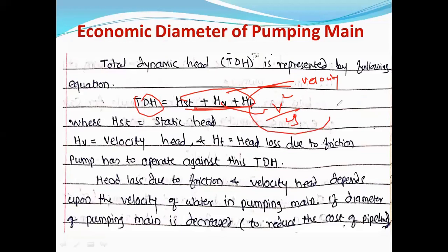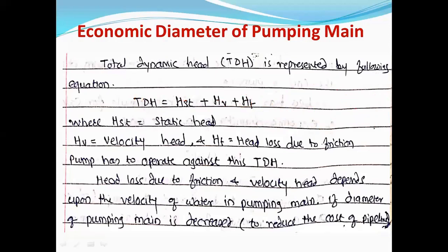The head loss due to friction is also dependent on velocity — from the Darcy-Weisbach equation: hf = 4fLv²/2gD. In this equation, the head loss hf is directly proportional to the square of velocity. So as velocity increases, head loss due to friction and velocity head both increase. As these two heads increase, the total dynamic head increases, and the pump has to provide more power and utilize more electricity to overcome this head.